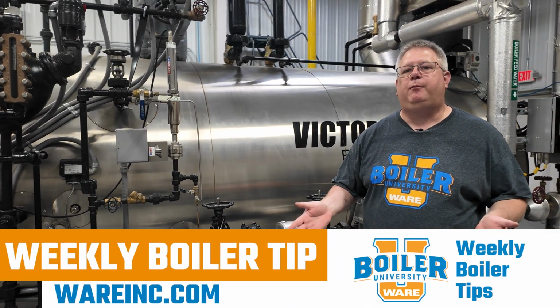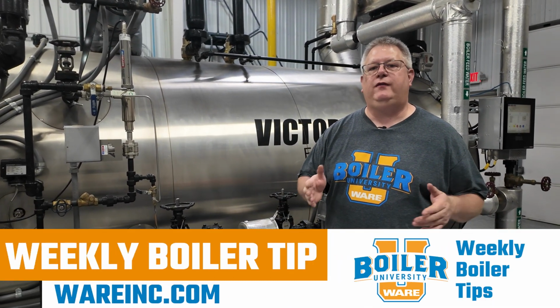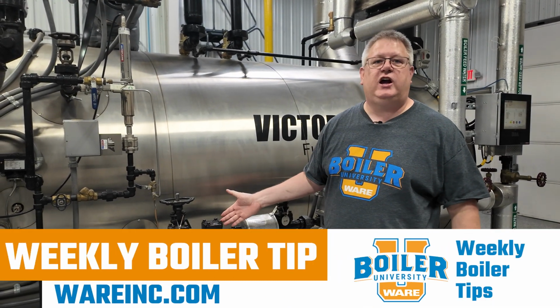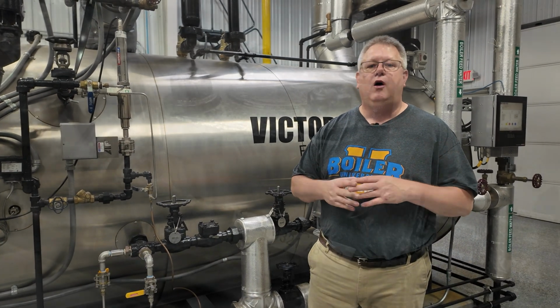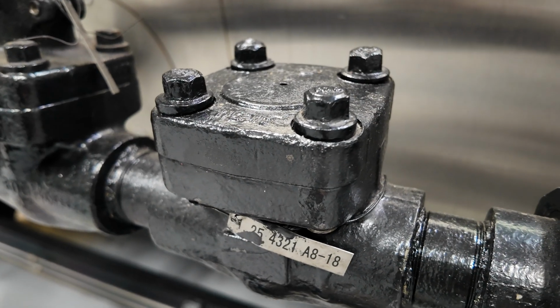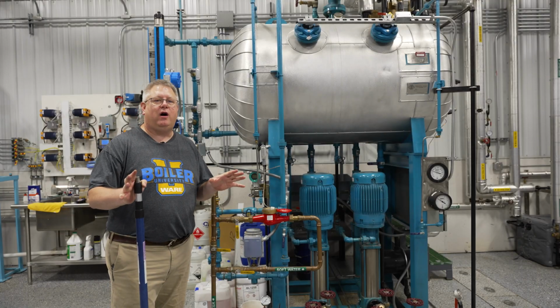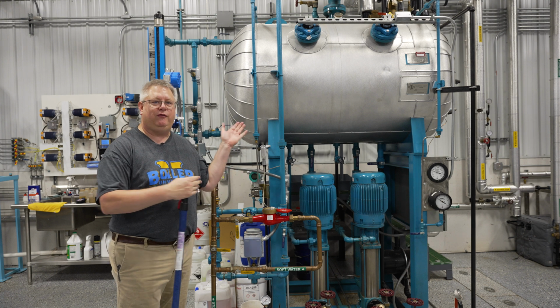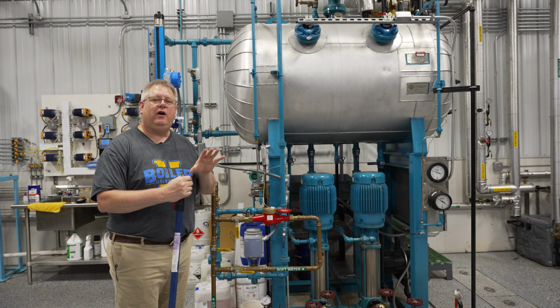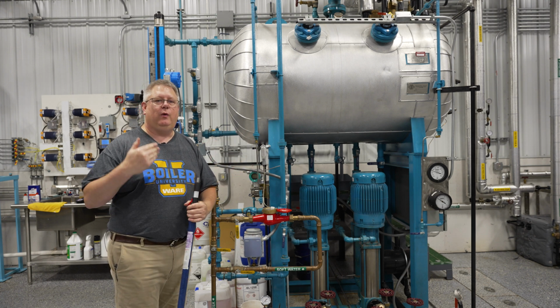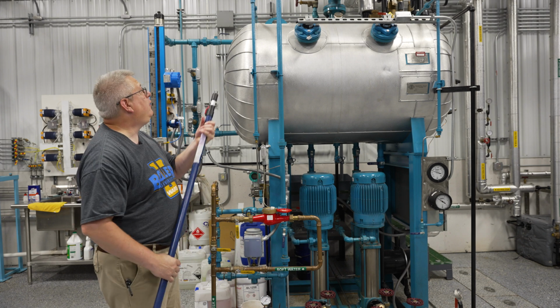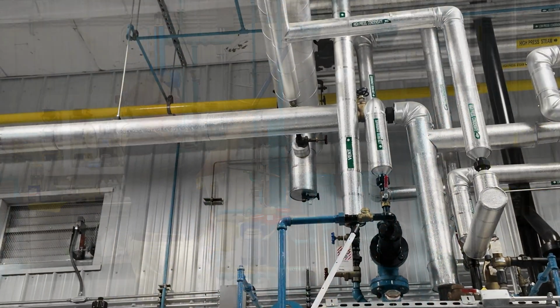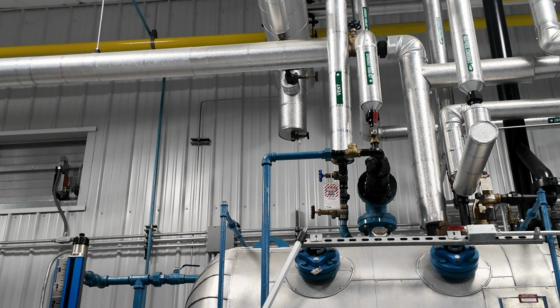On this week's boiler tip, we're going to look around the boiler room at different places that we've got check valves and talk about what they're doing in each case. If we follow the path of water from the water softeners to our feed system, this deaerator, there are several locations where we have check valves here. The first one being where the soft water goes to the deaerator.